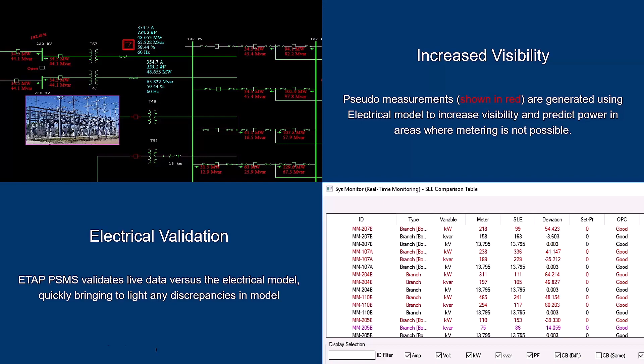In this demo, we can see the electrical model now displaying data from all electrical devices with live measurements. Since we have live data along with an electrical model containing nominal data, impedances, ratings, typical loading, etc., ETAP PSMS can predict the power flow across the rest of the model. These new measurements, displayed in red, indicate the estimated power flow where metering is not possible. The state and load estimation feature predicts these measurements across the model.